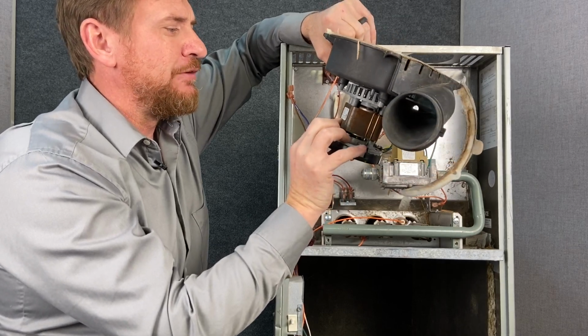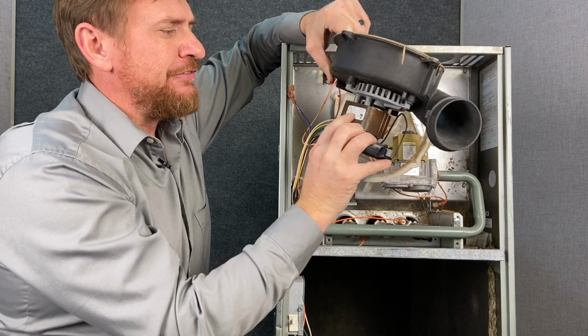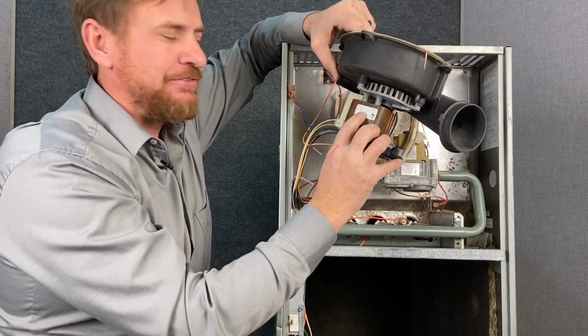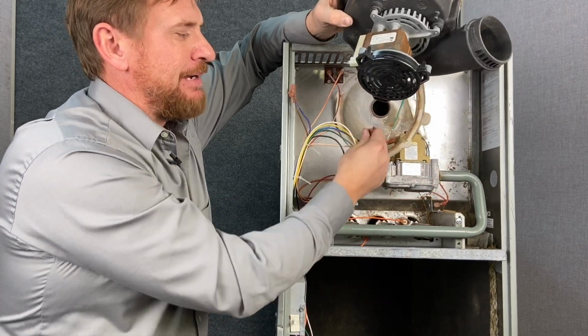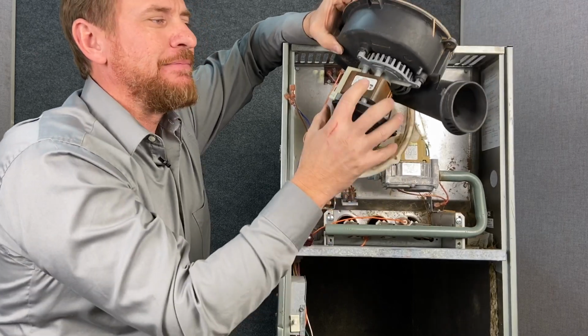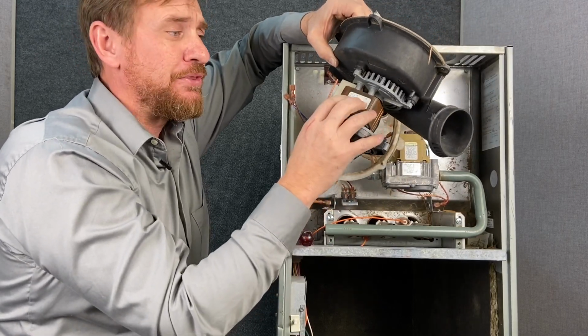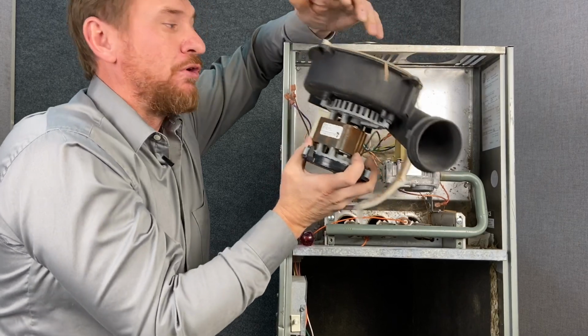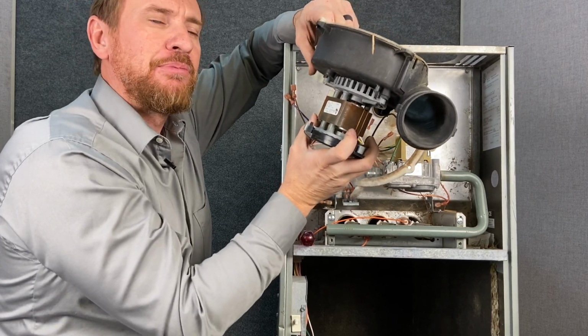And so this one is a 1/20th horsepower, but it's rated for 1.7 amps. So what we want to do is, while this is running, clamp our meter around one of these wires and see to make sure it's not drawing more than that. If it's drawing more than that, we're going to need to replace this motor or maybe check the heat exchanger to see if there's some other problem.